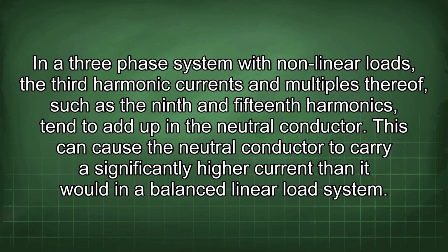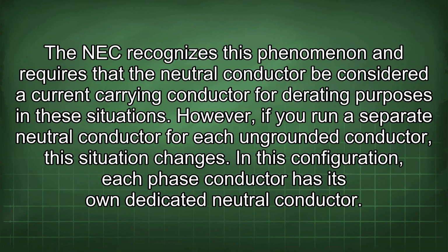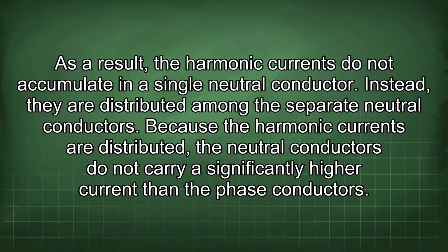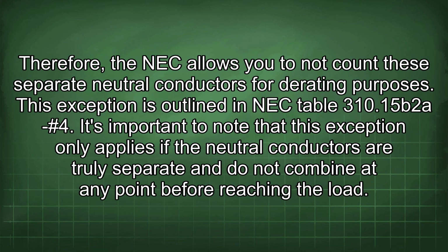This can cause the neutral conductor to carry a significantly higher current than it would in a balanced linear load system. The NEC recognizes this phenomenon and requires that the neutral conductor be considered a current-carrying conductor for derating purposes in these situations. However, if you run a separate neutral conductor for each ungrounded conductor, this situation changes. In this configuration, each phase conductor has its own dedicated neutral conductor. As a result, the harmonic currents do not accumulate in a single neutral conductor. Instead, they are distributed among the separate neutral conductors. Because the harmonic currents are distributed, the neutral conductors do not carry a significantly higher current than the phase conductors. Therefore, the NEC allows you to not count these separate neutral conductors for derating purposes.